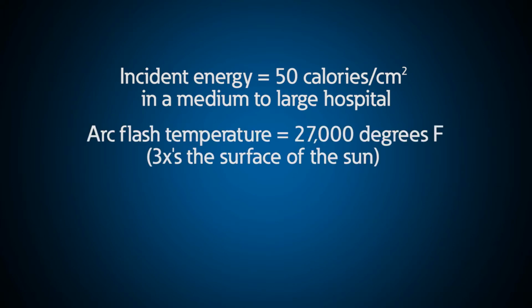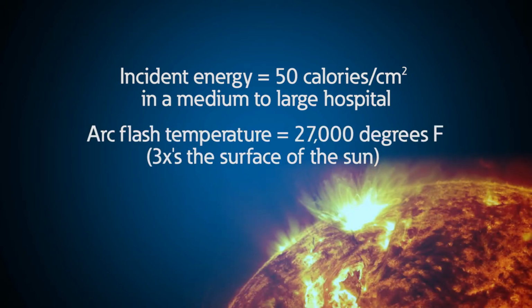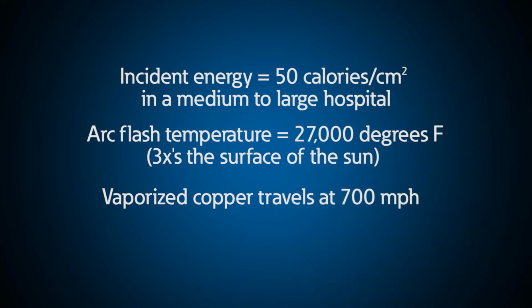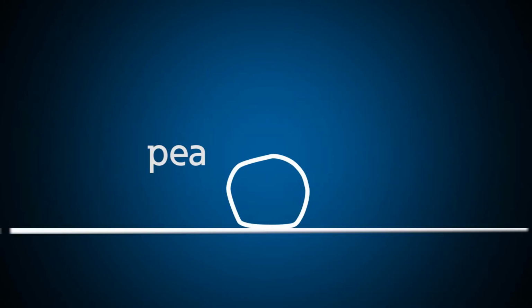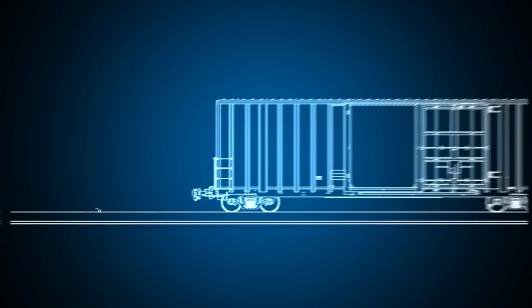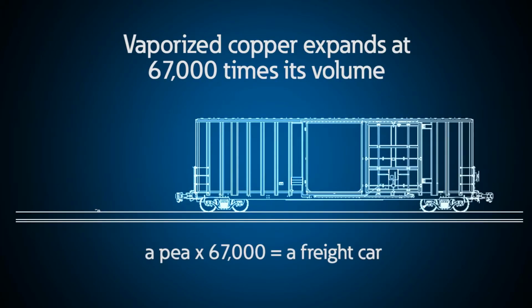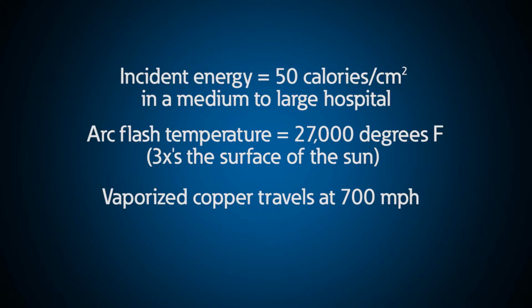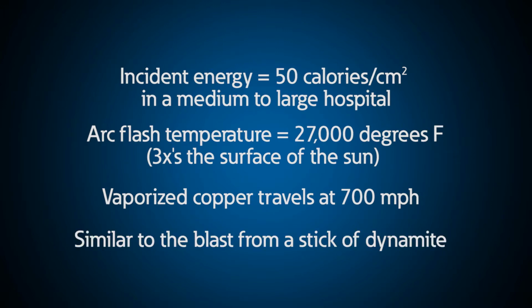The temperature from that arc could reach 27,000 degrees Fahrenheit, or close to 3 times the surface of the sun temperature. With that amount of energy, the vaporized copper would be traveling at speeds greater than 700 miles per hour. To imagine the amount of pressure created, picture a pea-sized piece of copper vaporizing to a point that it would fill a railroad car.